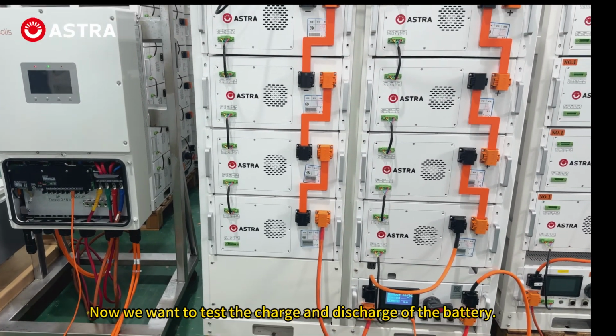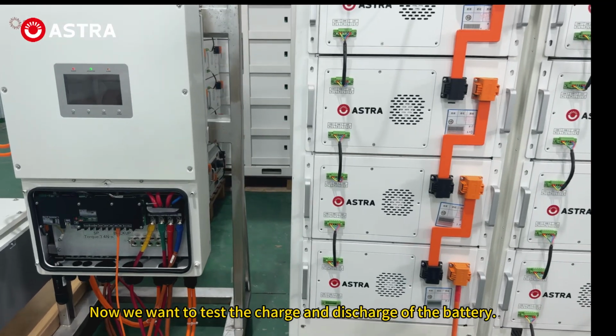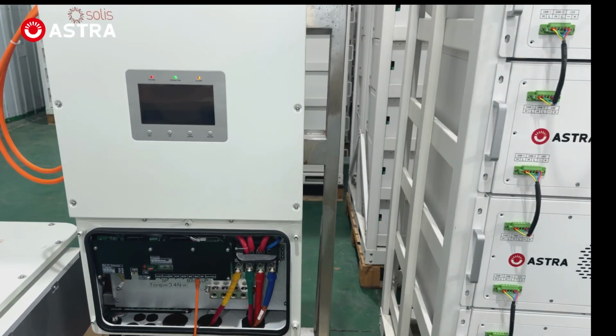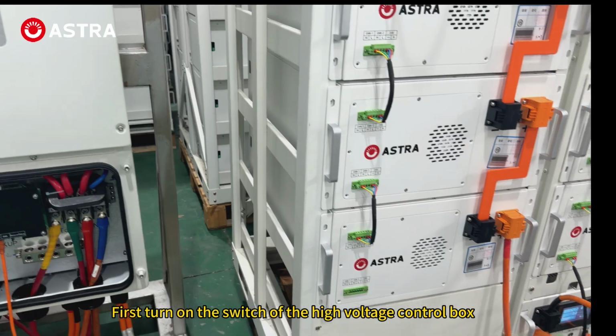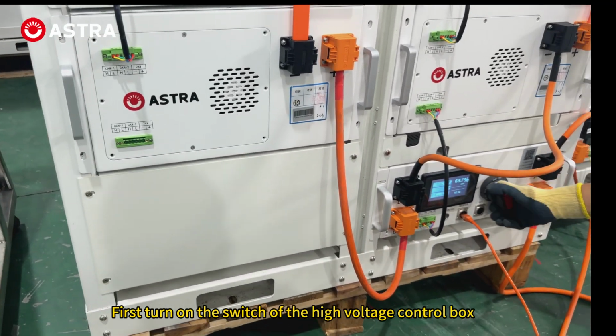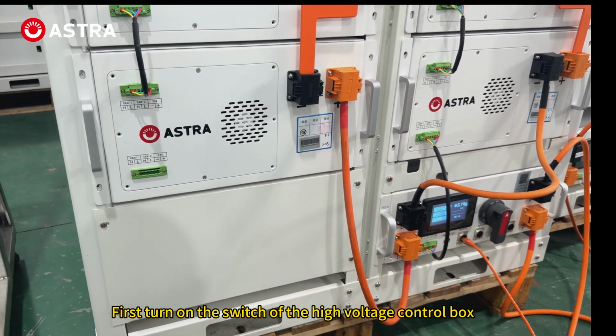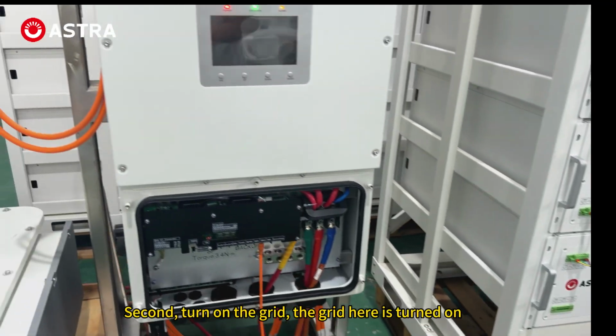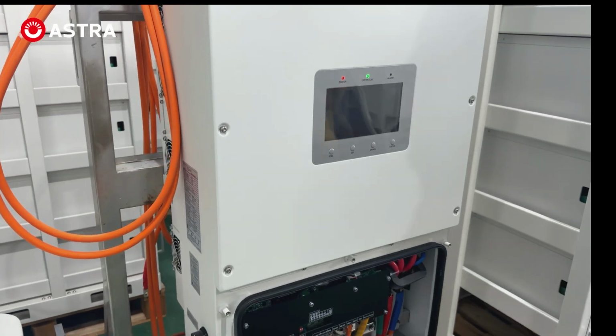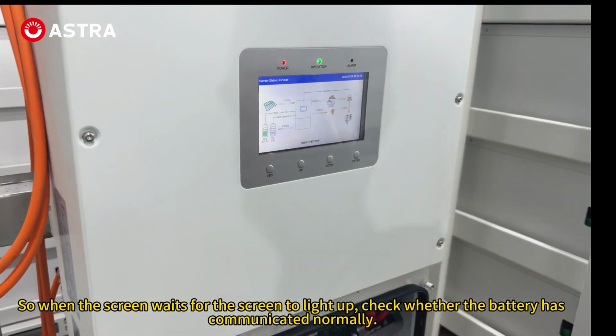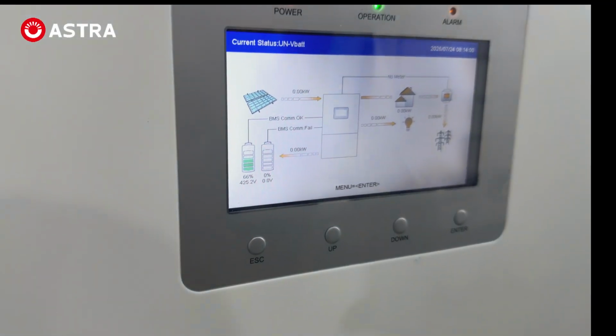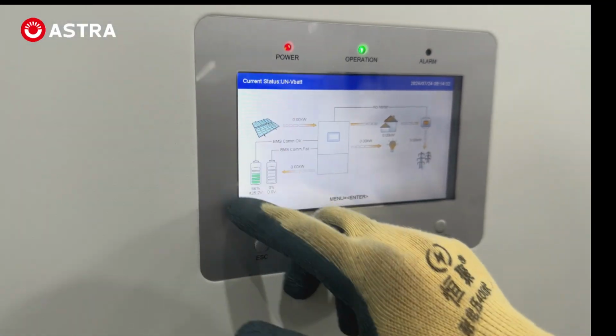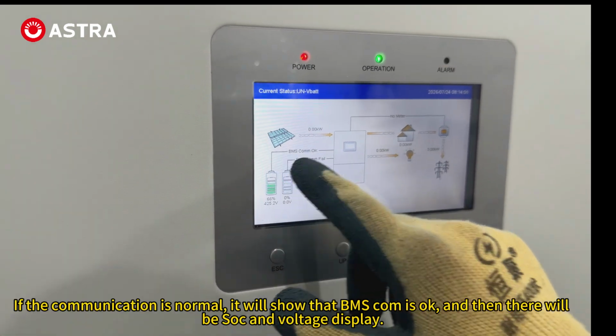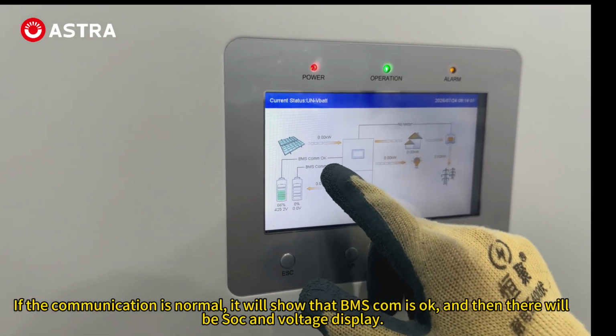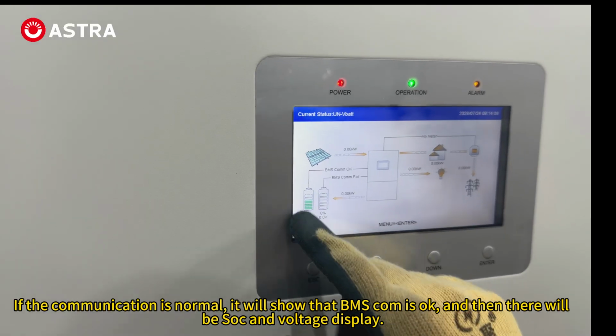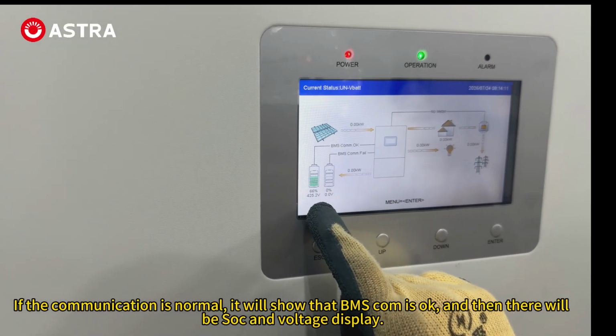Now we want to test the charge and discharge of the battery. First, turn on the switch of the high voltage control box. Second, turn on the grid. The grid here is turned on. So when the screen lights up, check whether the battery has communicated normally. If the communication is normal, it will show that BMS COM is okay, and then there will be SOC and voltage display.